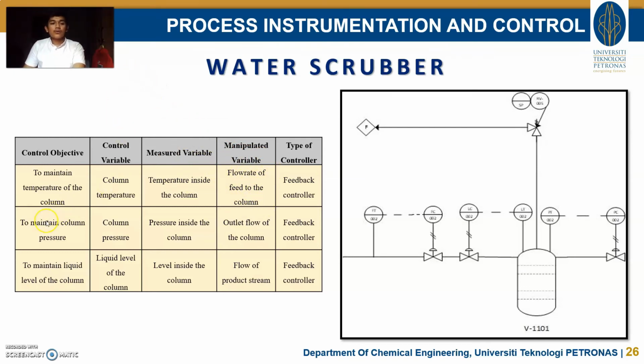For second one is to maintain column pressure. The measure variable is the pressure inside the column. So the manipulated variable here is outlet flow of the column. And the last one is to maintain liquid level of the column. So the control variable here is liquid level of the column. What we measure here is level inside the column. The manipulated variable is flow of product stream.